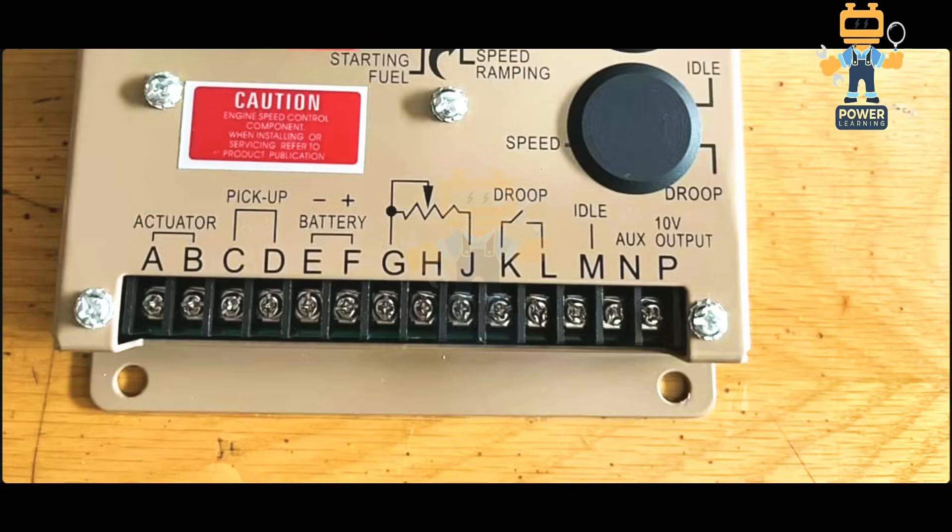After that, here we have K and L. This is for droop activation. If you are using this engine with droop function, you can connect your switch here for droop activation. If you close the switch, droop function is activated. If you open the switch, the droop functionality is off. After that, idle is on number M. Idle speed you can select from the idle terminal - you can connect cable here on idle and you can select the idle speed.